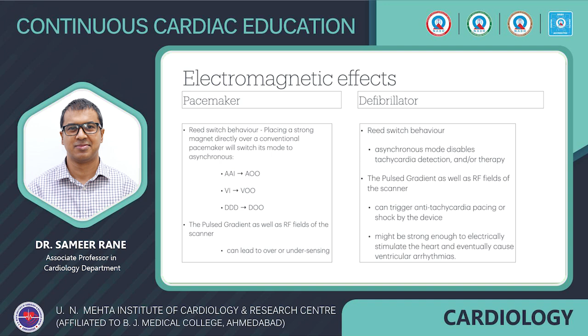Generators have been designed to have reduced ferromagnetic content, and reed switches have been replaced with Hall sensors, with shielding and filters to reduce the risk of damage to the circuit and internal power supply, and a dedicated MR programming pathway to be turned on and off before and after the scan.